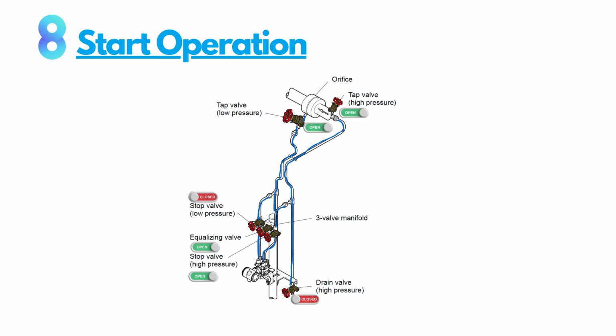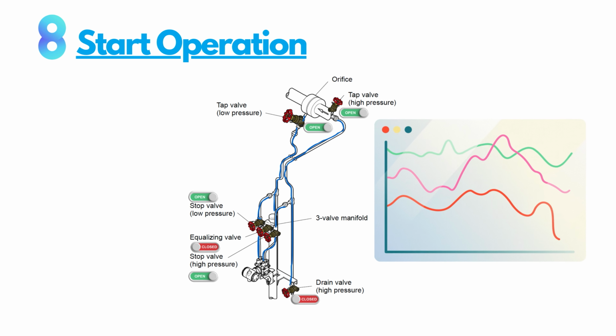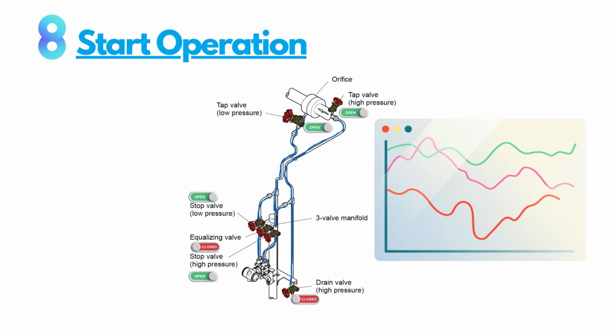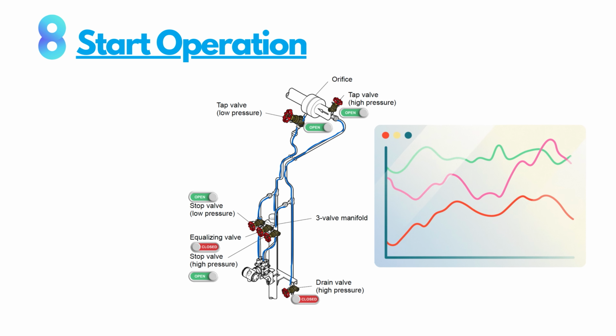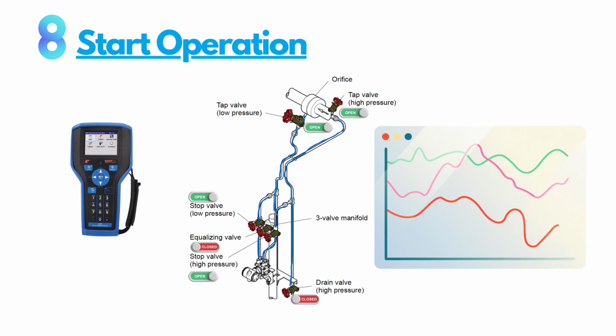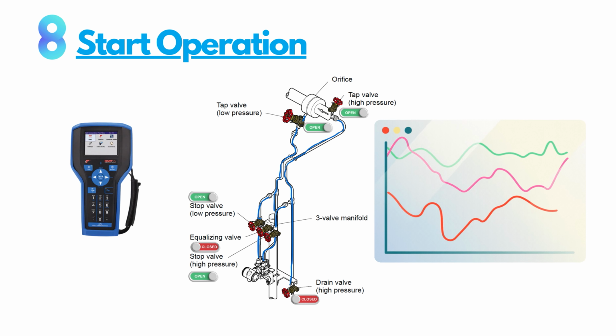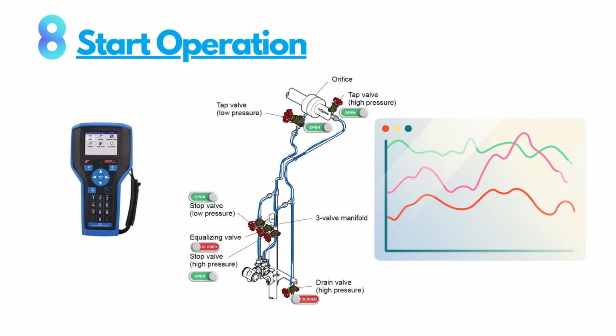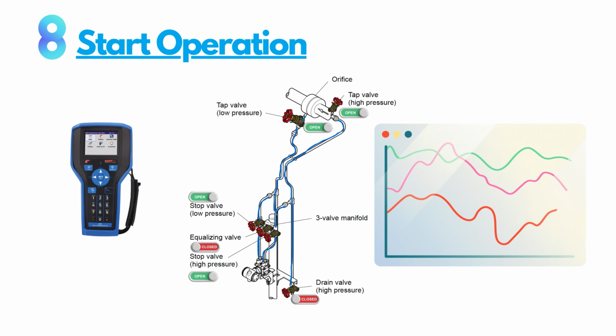Step 8. Start operation. Follow the procedure below to start operation. 1. Close the equalizing valve. 2. Gradually open the low pressure stop valve. This places the transmitter in an operational condition. 3. Confirm the operating status. If the output signal exhibits wide fluctuations, hunting, due to periodic variation in the process pressure, use the HART communicator to dampen the transmitter output signal.